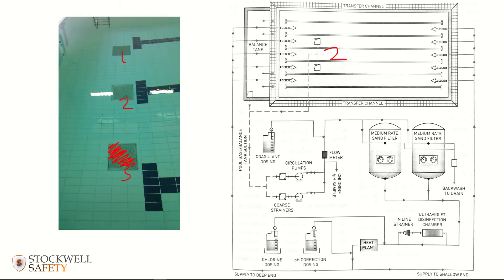The other sumps were much larger, which makes it more difficult to form a seal. Multiple sump outlets also need to be at least two metres apart. Having more than one sump is a key control measure that reduces the risk.